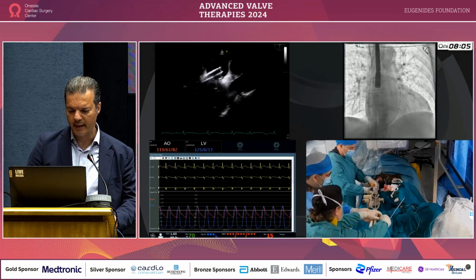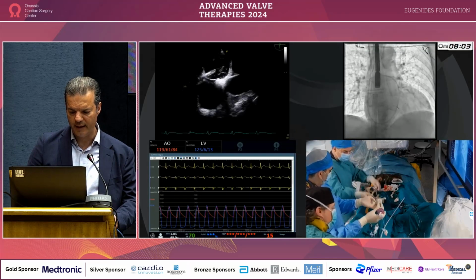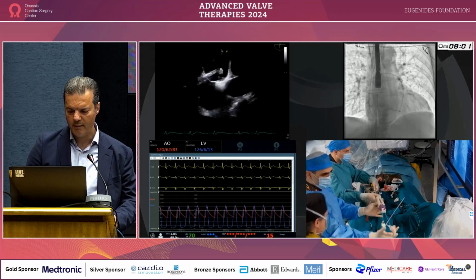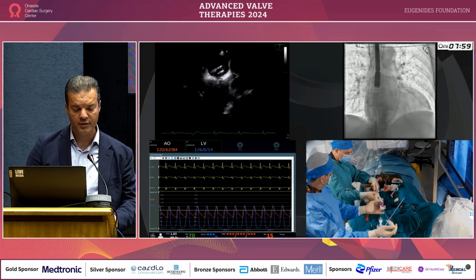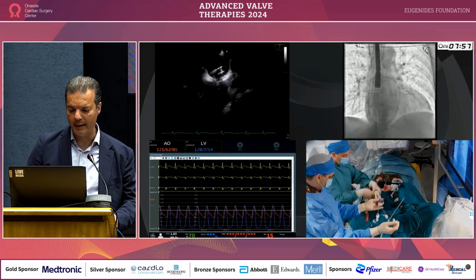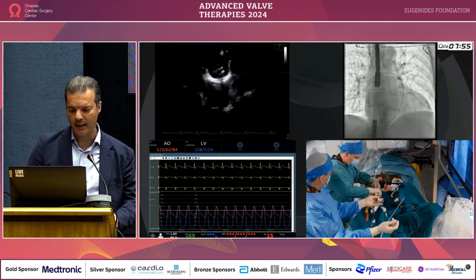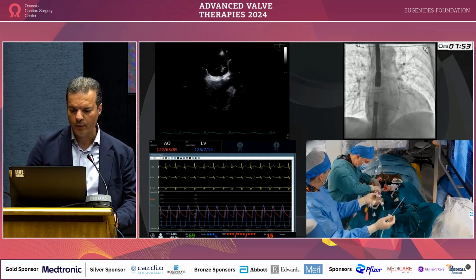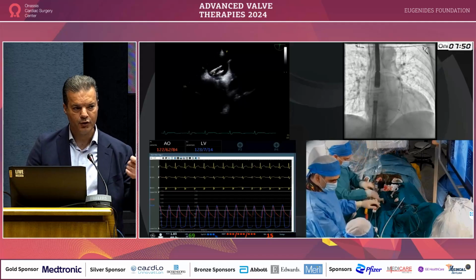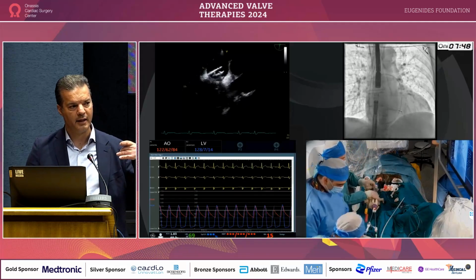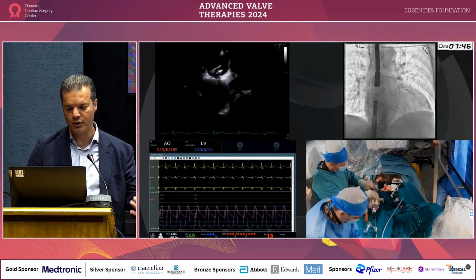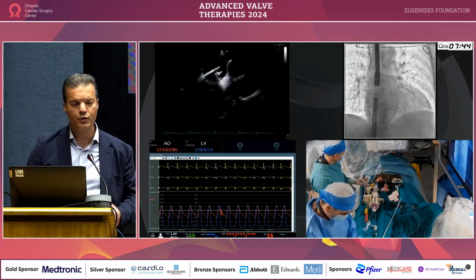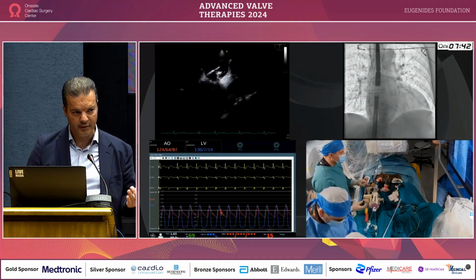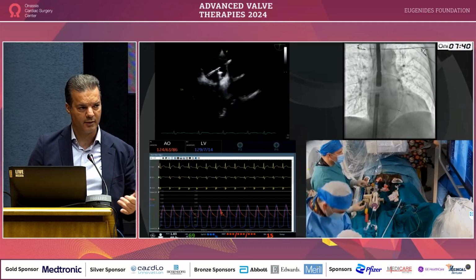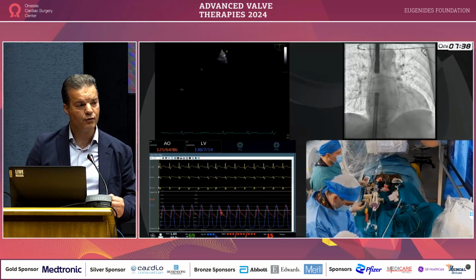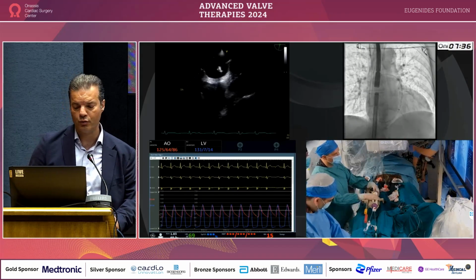Then the delivery catheter is introduced under flushing, and the aim is to advance it to the tip of the steerable guide catheter, so align the inner catheter with the outer catheter. So the interesting thing is that there is a dual catheter design. You have the outside catheter, which is a steerable sheath, and the inside catheter, which is the inner catheter. So when you unsheath the valve, you unsheath both catheters, one after the other. And that gives you excellent control of the position of the cage.